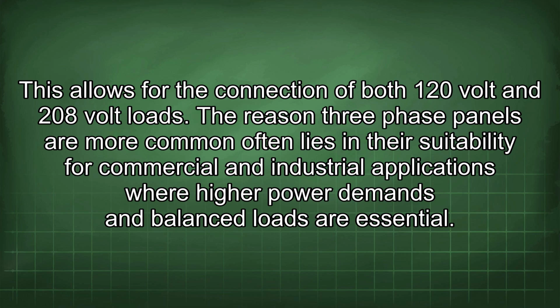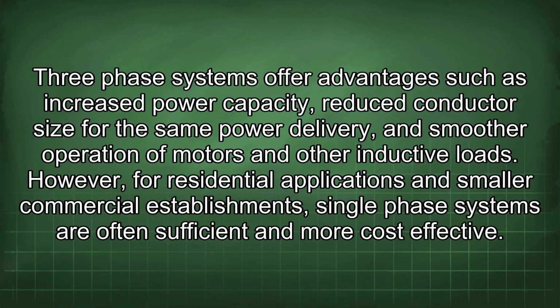The reason 3-phase panels are more common often lies in their suitability for commercial and industrial applications where higher power demands and balanced loads are essential. 3-phase systems offer advantages such as increased power capacity, reduced conductor size for the same power delivery, and smoother operation of motors and other inductive loads. However, for residential applications and smaller commercial establishments, single-phase systems are often sufficient and more cost-effective.